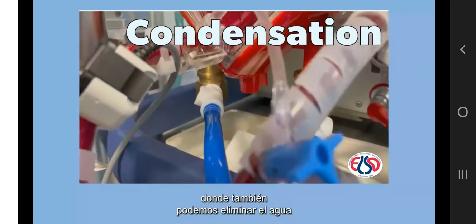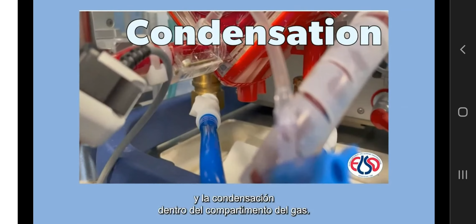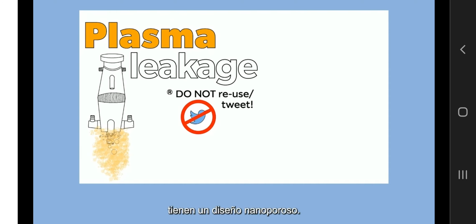And here we have another kind of membrane lung. And again, we could purge the water, the condensation inside the gas compartment. The risk of plasma leakage, which is the leakage of plasma from the gas outlet of the oxygenator, is negligible with polymethylpentene membranes, the most widely used membranes for ECMO nowadays. This is because polymethylpentene fibers have a nanoporous design.